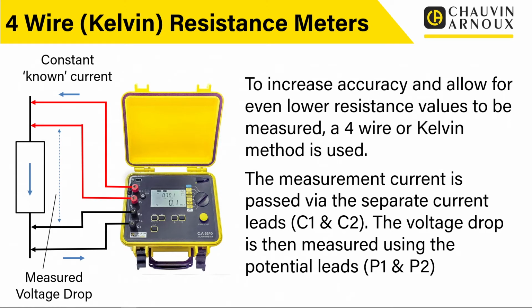So what we have is our constant known current circuit. When you look on the tester, we have our current terminals, C1 and C2, and they pass a current through the resistance under test. And then we use two potential terminals, P1 and P2, to measure the volts drop. So the good thing is we've got the current circuit. Now that current circuit is separate, so we could be passing a big chunky current through that circuit, and that can be measured. So by passing the current and measuring what the current is, things like contact resistance don't really matter, because we know what current is traveling through there, and we're measuring it separately.